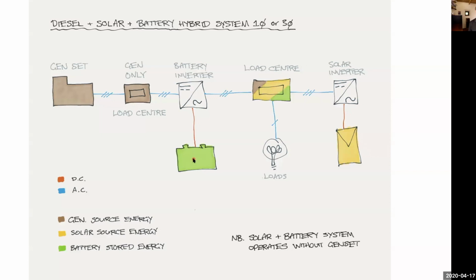The advantages of this are many, and you can, for instance, have them in different locations. You don't have to co-locate your equipment. For instance, let's say you're on a rural property and you've got a shed out the back, which is where you want to put the batteries because they're space hungry and you don't really want them in your lounge room, nor are you allowed to anymore in Australia and New Zealand. You might want to put them in that back shed, but the back shed is covered with trees all around it and shady and cool, which is actually quite good for most batteries, but it's no good for solar. But there is a submain that goes out to that back shed. So the solar inverter could be on the main house where the sun is shining and it can generate efficiently without shade. And so the energy can flow across that submain to the back shed. So no co-location, it's a bit of a plus.